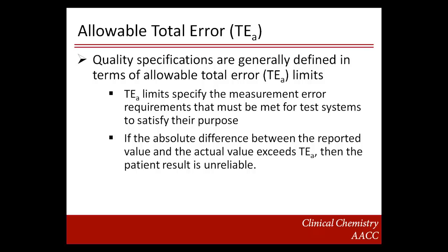The allowable total error limits specify the measurement error requirements that must be met for patient results to be fit for use. Every patient result has some kind of measurement error, even when the test system is in control. But if there is an out-of-control condition, additional error is added. If the difference between the value reported and the actual value is greater than the specified allowable total error limit, then we consider the patient result unreliable.